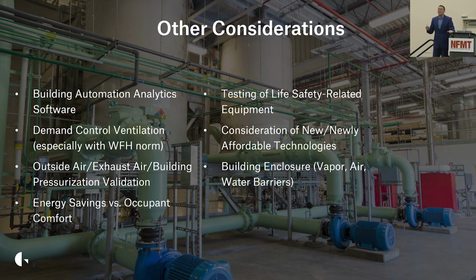So building automation systems are a little bit simpler. They may have some rudimentary alarms that tell you when something's wrong, but really the analytics software will tell you, you need to optimize your chilled water system, in this way you should be changing this or that, or they'll take a group of metrics and use the aggregate of those metrics to tell you that you need to change something, or that maybe something is wrong - whereas a single sensor won't tell you that. That's kind of my best explanation of that software. I've seen it poorly implemented - it can end with nuisance alarms, bad information, and just bad intelligence. So I don't want to say don't do it, but if you do it, make sure you know what you're doing. Make sure you trust the people you're paying to implement it. Probably you want an ongoing relationship with those people, not just a one-time purchase.